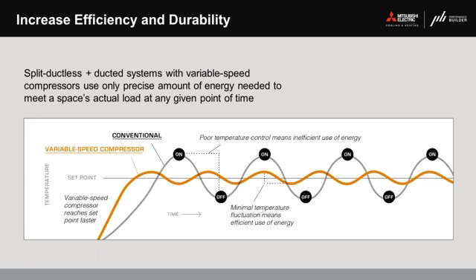That means you're only using as much energy as the house requires. Remember, the load calculation characterizes the peak needs of your house, but you're usually not seeing those peak conditions. In fact, you only see that about 1% of the year. That's how we design these systems, and that's how we do a Manual J, using the 1% design condition.